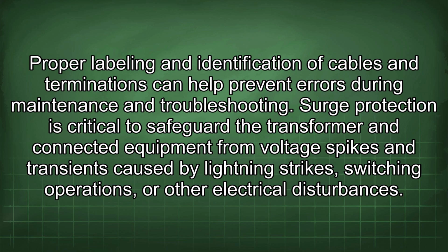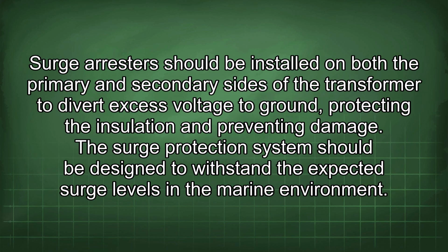Surge protection is critical to safeguard the transformer and connected equipment from voltage spikes and transients caused by lightning strikes, switching operations, or other electrical disturbances. Surge arresters should be installed on both the primary and secondary sides of the transformer to divert excess voltage to ground, protecting the insulation and preventing damage. The surge protection system should be designed to withstand the expected surge levels in the marine environment.